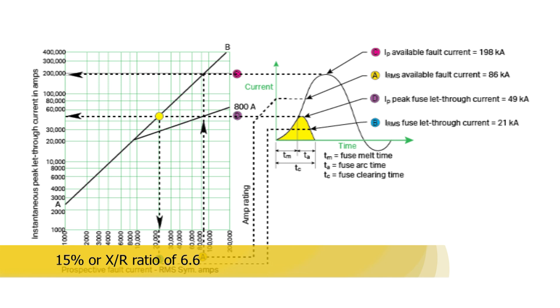The degree of current limitation of a particular fuse depends on the available fault current that can be delivered by the electrical system. This is shown for each fuse in the fuse let-through curves. The curves are plotted from actual test data in a circuit with a short circuit power factor of 15% or an X/R ratio of 6.6. This establishes the AB line. The fuse curves represent the cutoff value of the prospective available fault current under the given circuit conditions.